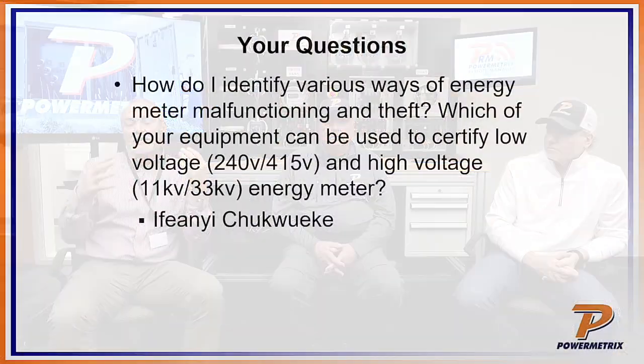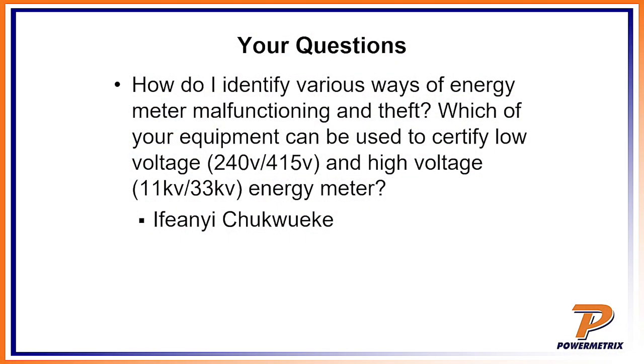And it's really the limitations for us wouldn't be on the meter side, it would be on the CT side and what we can get to with the CTs. But as far as catching a meter malfunction, can you do a customer load meter test? Yeah, very important. If someone has tampered with a CT, can you actually get on the primary and the secondary of the CT? That's right, to make sure that CT hasn't been tampered with.